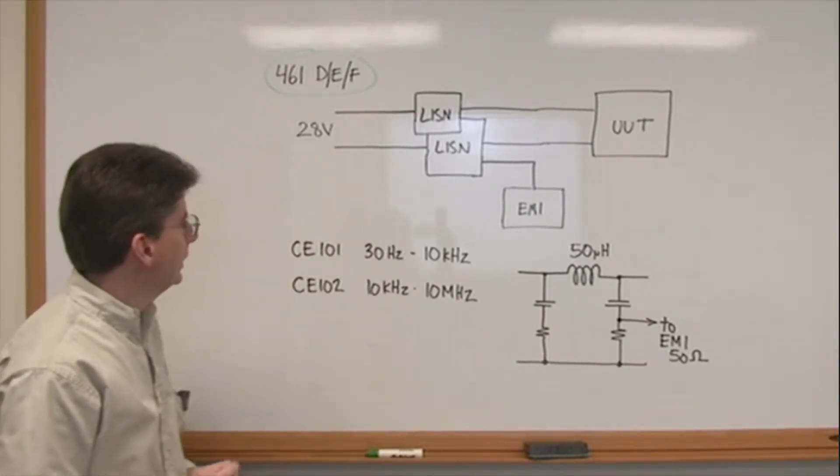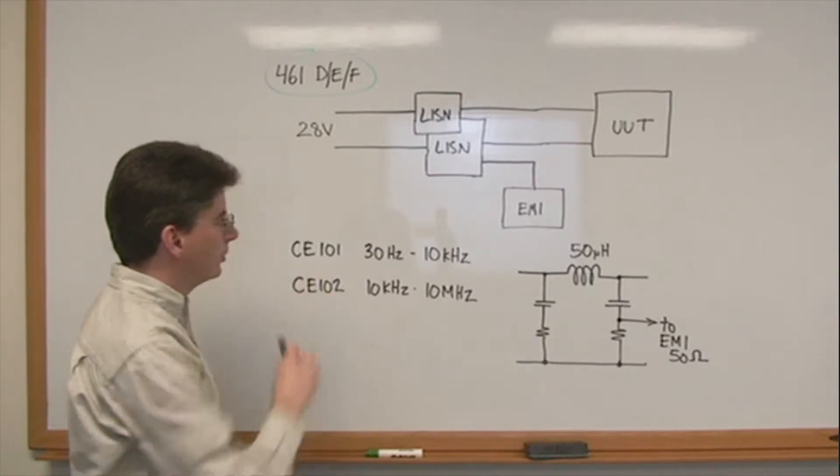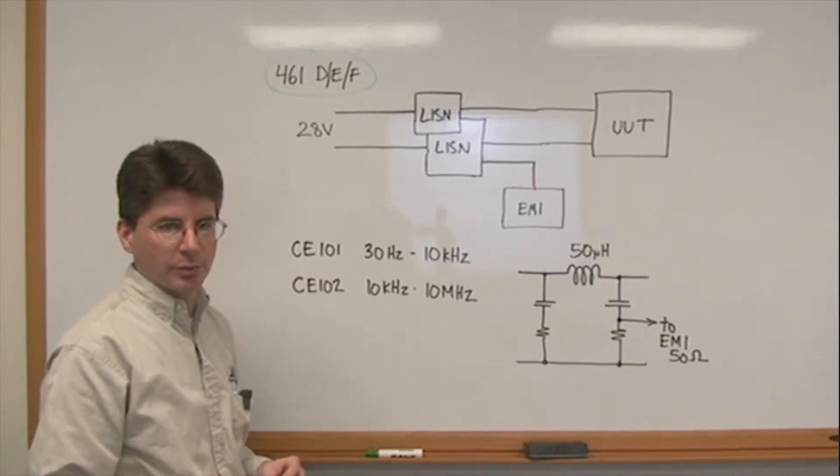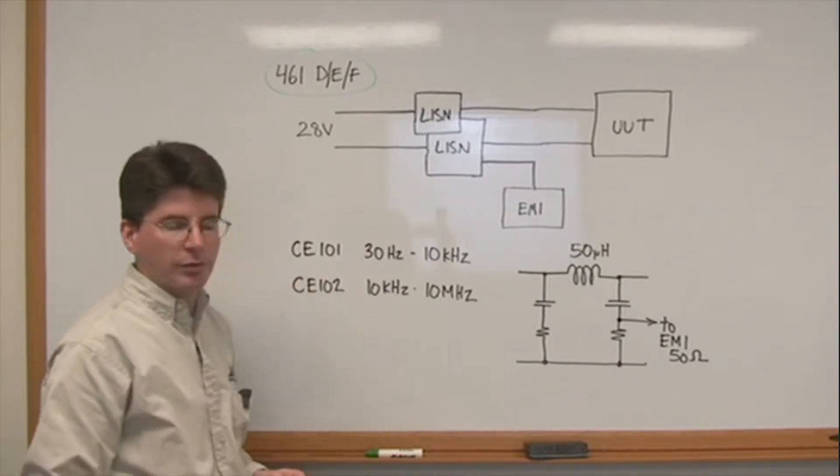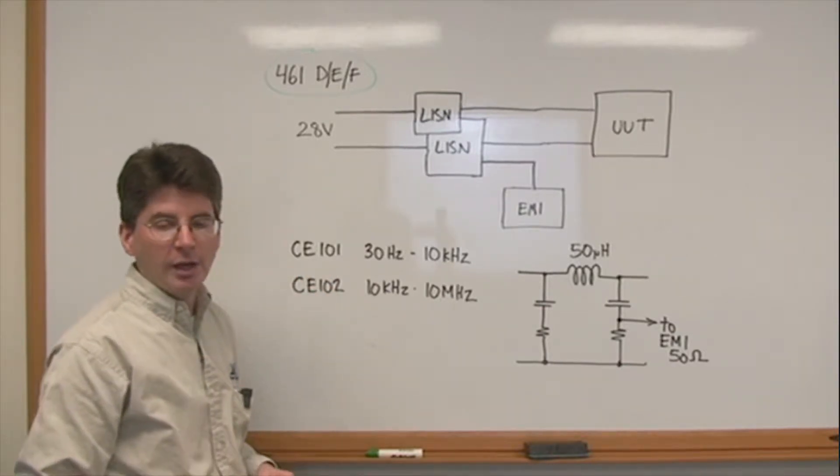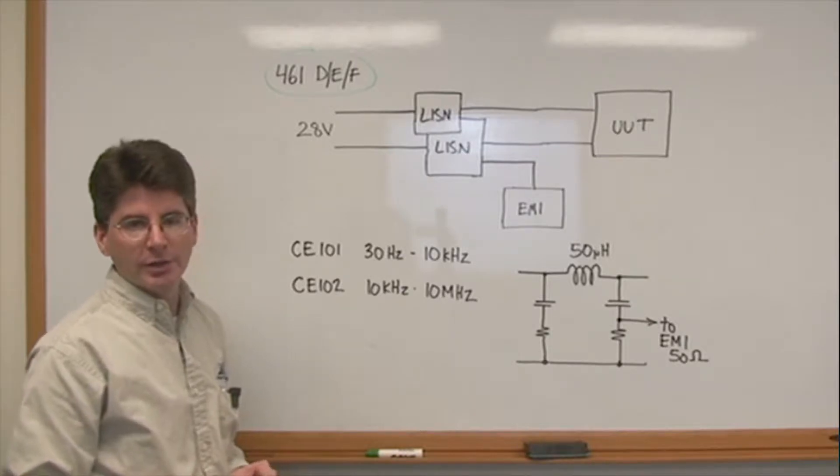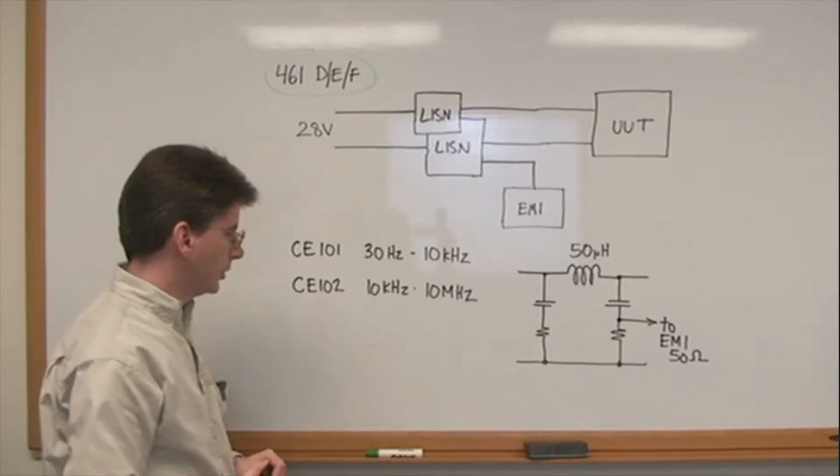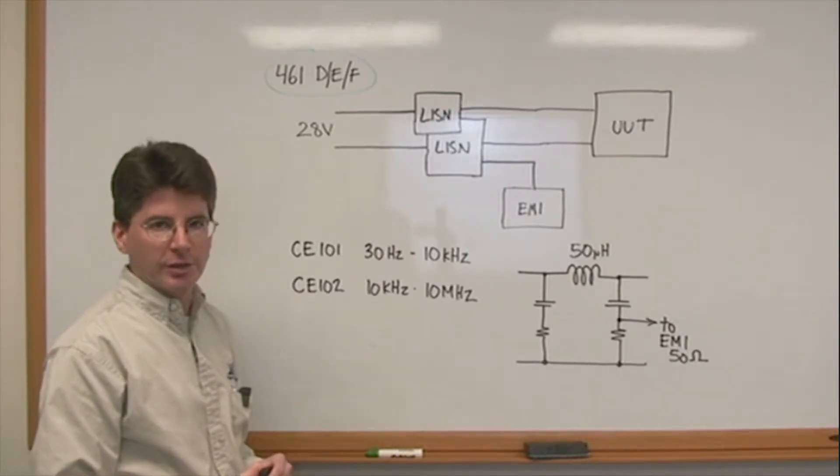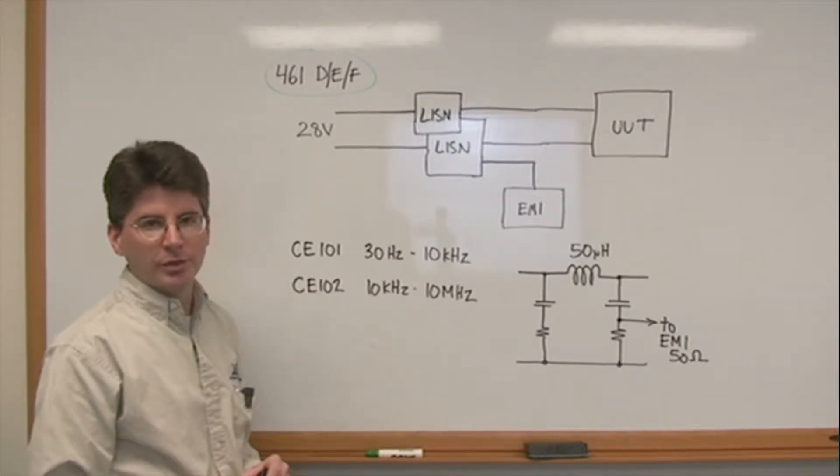In 461D, E and F there are two specs for conducted emissions which concern us. The first is CE-101, which is from 30 hertz to 10 kilohertz. Again, VPT's products do not emit any noise in this spectrum. The second is CE-102, which is from 10 kilohertz to 10 megahertz, and this is where we will be concerned.